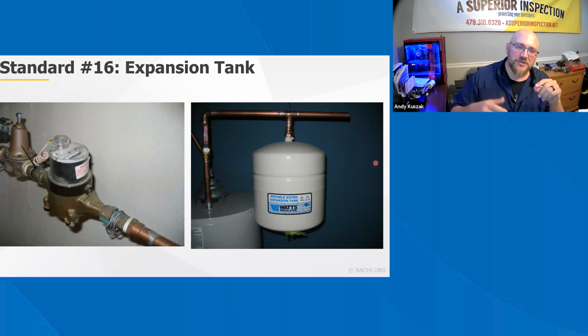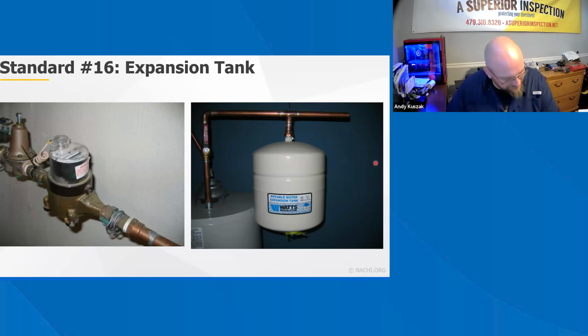But when you introduce, let's say you introduce a hot water, oh gosh, I just lost the name of it. So a hot water circulation pump. So where you circulate that water to the farthest fixture and it comes back, so you have continuous hot water at your fixtures. When you introduce that into a tankless water heater, then you do have to have a thermal expansion, because you've installed that water circulation pump, you've essentially created another closed system. And so that heated water has to have some place to expand to.